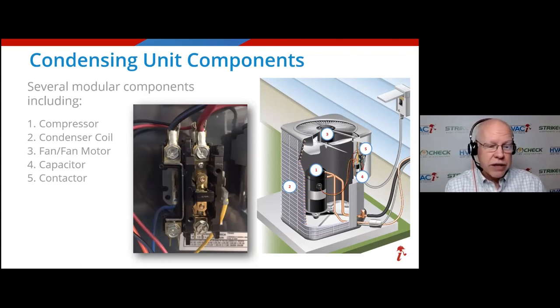Those smaller wires, the blue and the yellows, are coming from the thermostat and the control board, telling it when to turn on and when to turn off and things like that. So a lot can go wrong in the contactor, but guess what? Wear and tear is also a huge cause of loss that is attributed to the contactor. The contactor is a mechanical device. There's parts in there that are physically moving and making contact.